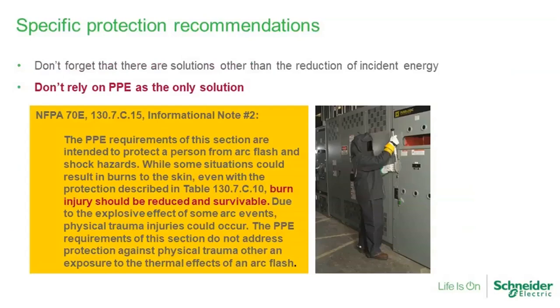And then last but not least, don't forget that there are solutions other than a reduction of incident energy, and don't rely on personal protective equipment as the only solution. The quote here from NFPA 70E: while PPE requirements for this section are intended to protect the person from arc flash and shock hazards, and then it goes on to say, even if you wear the stuff that it recommends in NFPA 70E, there is the possibility that you may sustain some kind of burn injury.